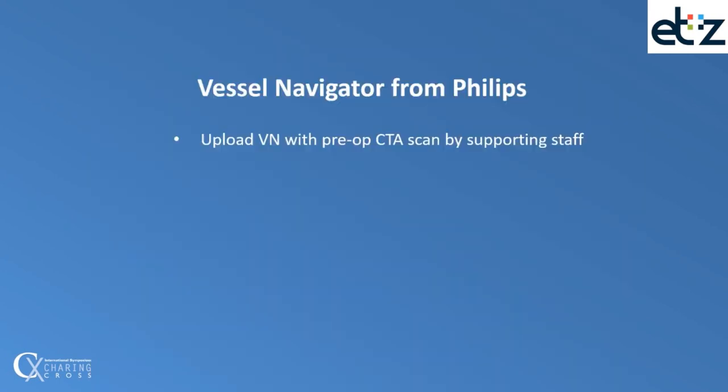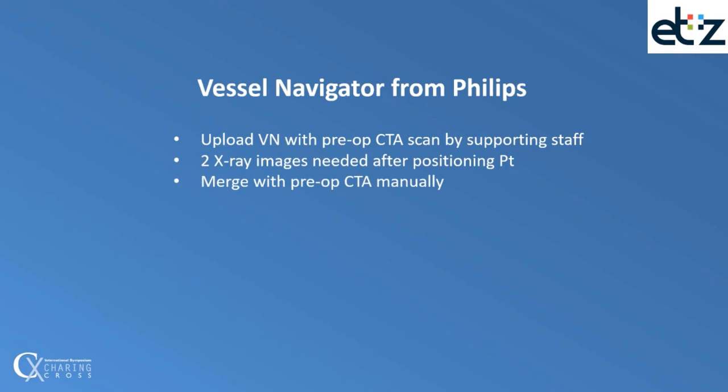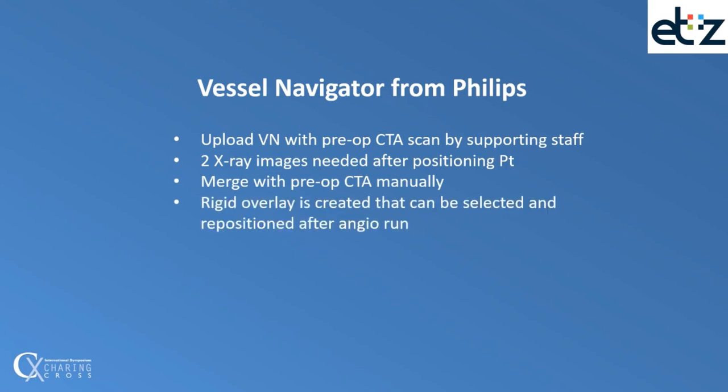In Vessel Navigator you have to upload the CTA scan. After positioning the patient, two x-ray images are needed to merge these data, and after merge you create a rigid overlay that can be selected and repositioned after an angio run. It is essential to realize that this overlay stays rigid.